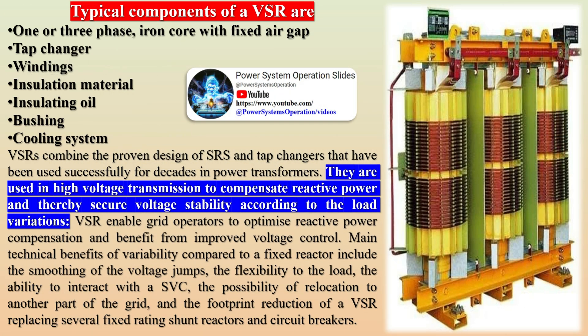For example, a VSR with a rating of 150 MVAR at 300 kV can today be regulated between 80 MVAR and 150 MVAR. Typical components of a VSR include: one or three-phase iron core with fixed air gap, tap changer, windings, insulation material, insulating oil, bushing, and cooling system.